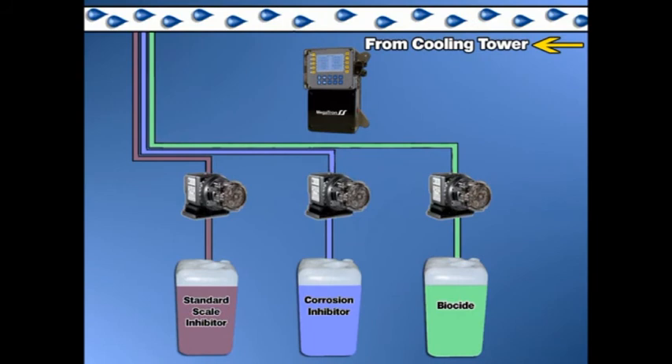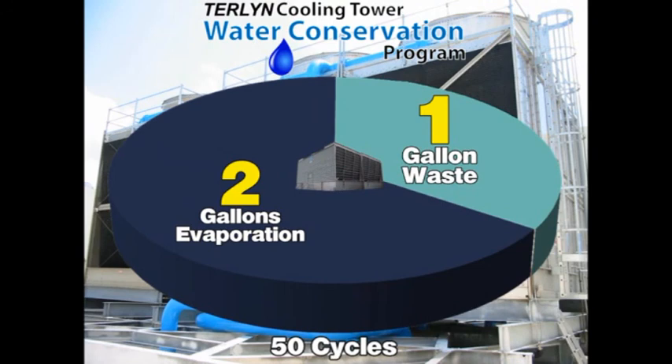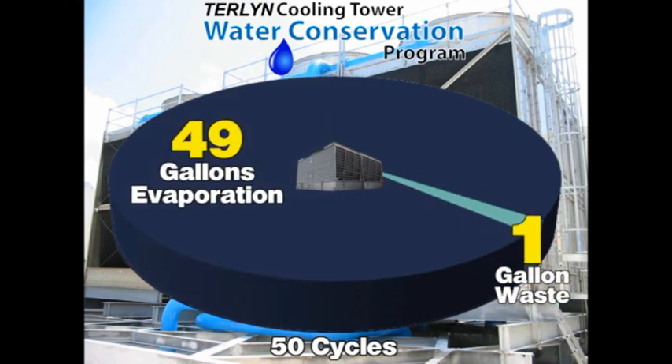The Terlyn program incorporates industry standard corrosion inhibitors, biocides, and feed equipment. As a result, upgrading to our advanced water conservation technology is as easy as replacing one treatment with another. Utilizing the Terlyn program at 50 cycles of concentration requires only one gallon of wastewater for every 49 gallons of water that are evaporated. This reduces cooling tower wastewater discharge from 33% of the total water used to only 2%.